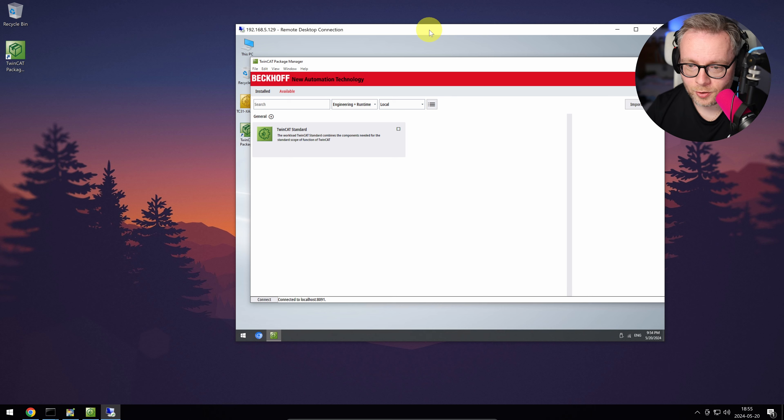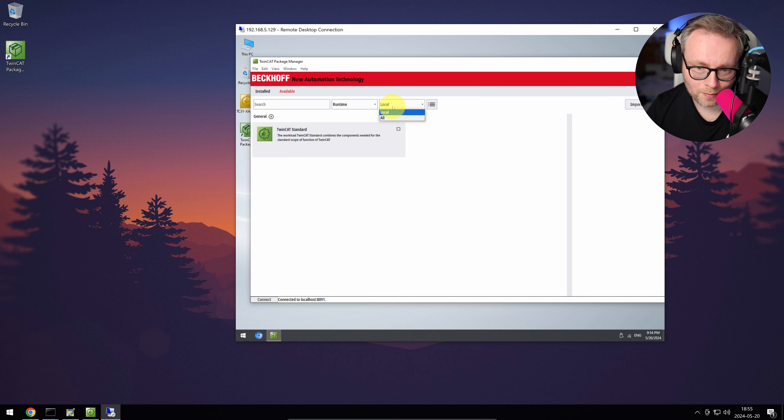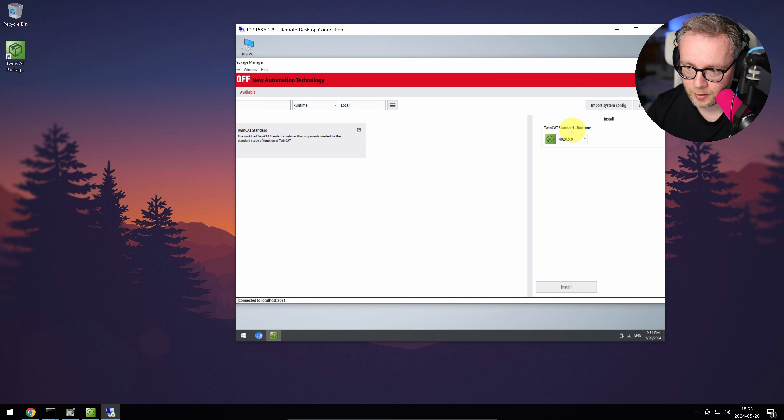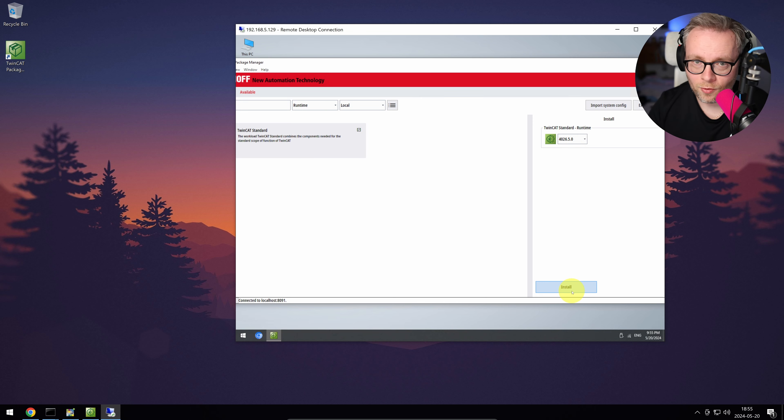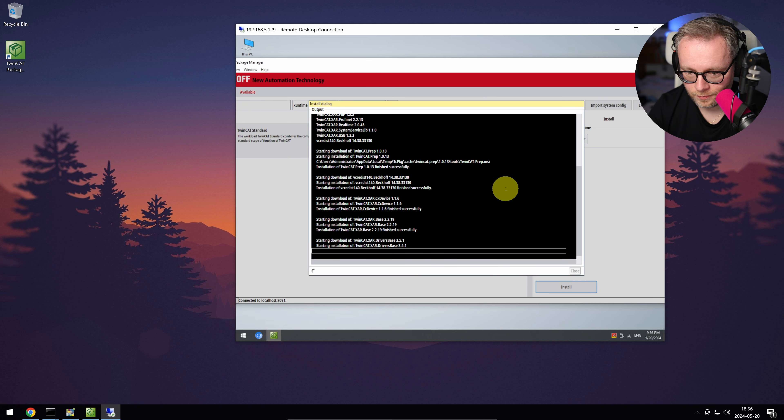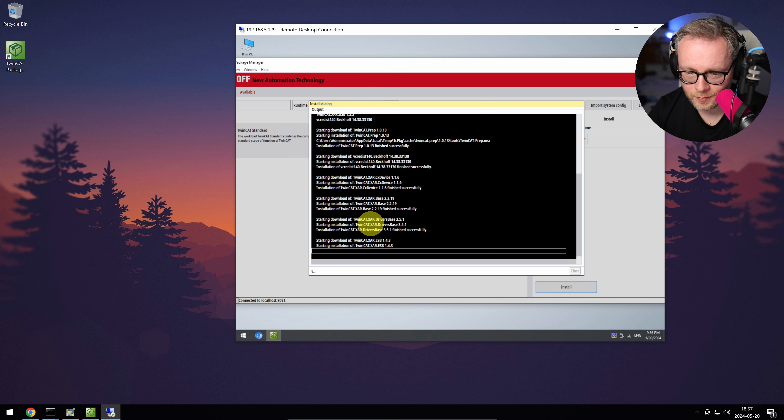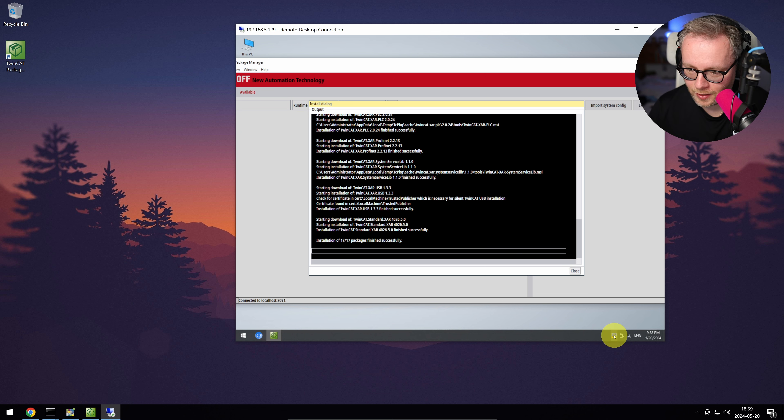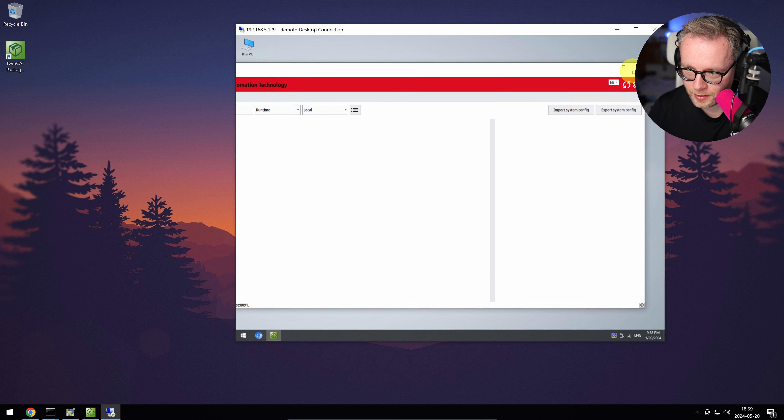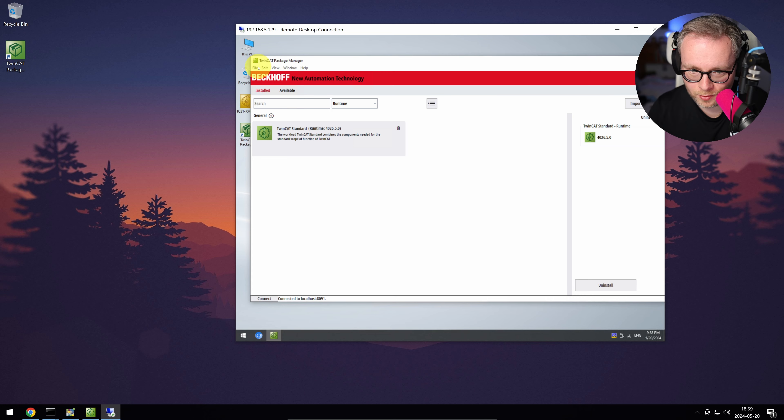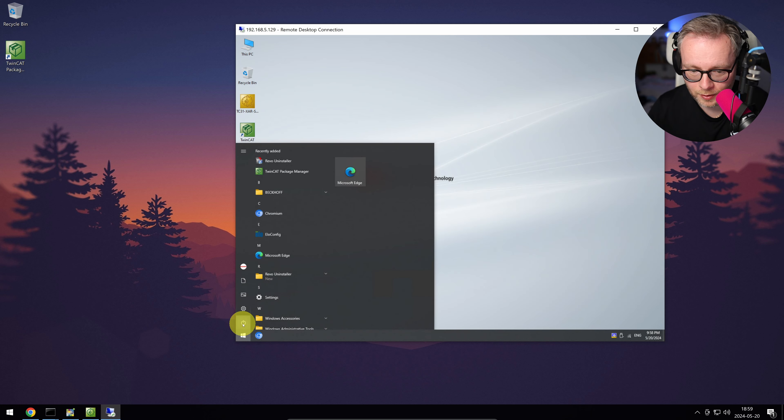So I added the local source. I'm only interested in installing the runtime here. This is my feed, by the way, the local that we added before. Now we have the TwinCAT standard here and we only have the runtime and that's what we want. So I want to install the runtime now. And again, it is going to install it from my USB stick now. So install. Yeah, here we can see that drivers are installed. Okay, installation of 17 out of 17 packages finished successfully. And we can actually even see the TwinCAT icon down here for the runtime and the AMS router. I'm going to close and now we can see the runtime is installed. I'm going to exit this guy and I'm going to reboot the PLC.